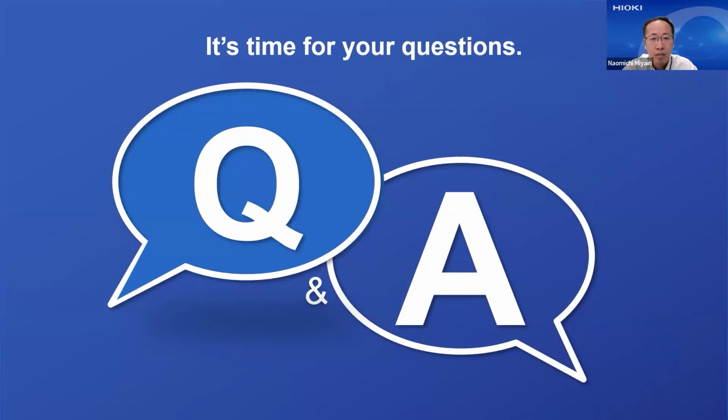Saito-san, thank you. I will translate into English. One of the main advantages of power analyzers over oscilloscopes is their ability to provide stable and long-term measurements without issues such as temperature drift or channel-to-channel phase differences.